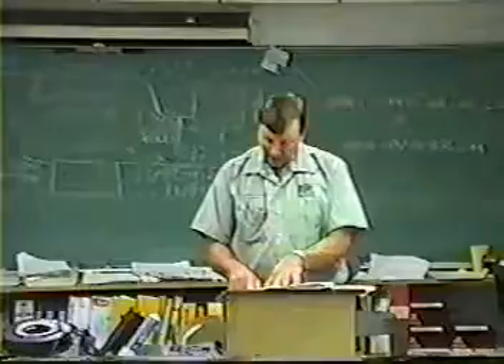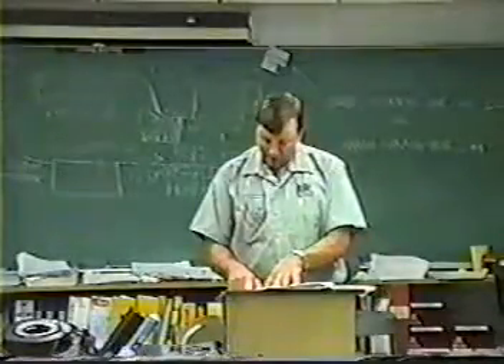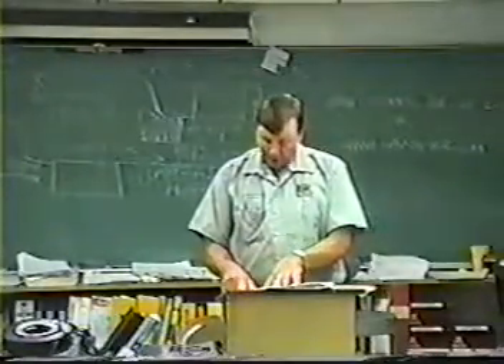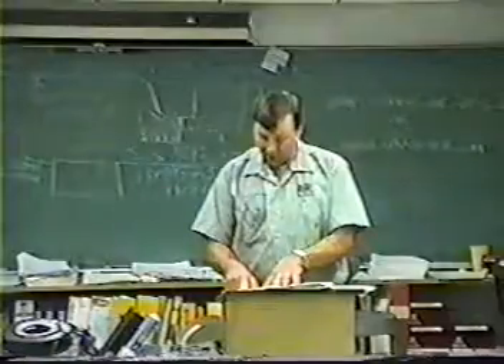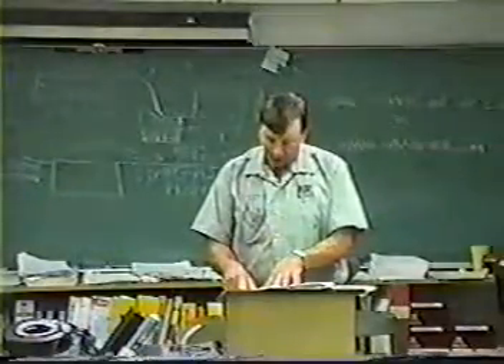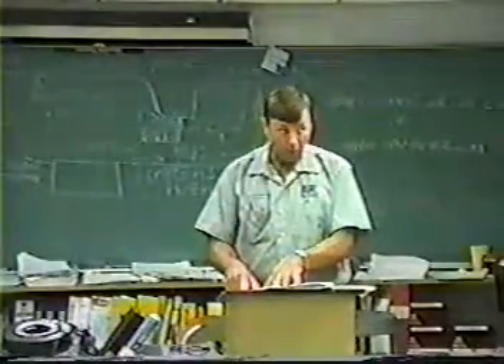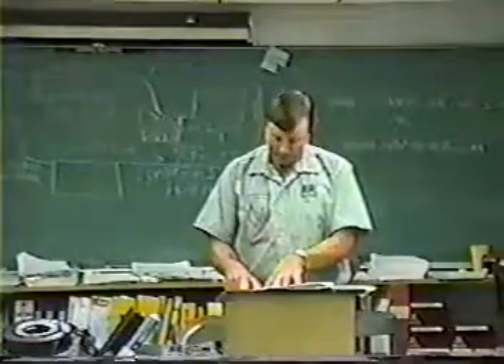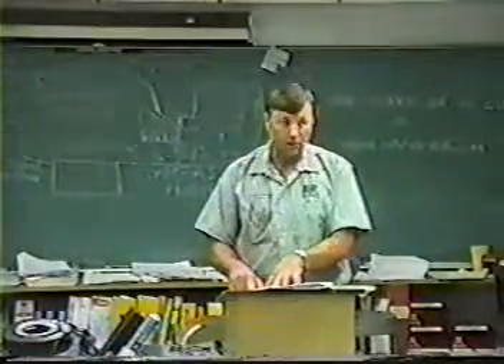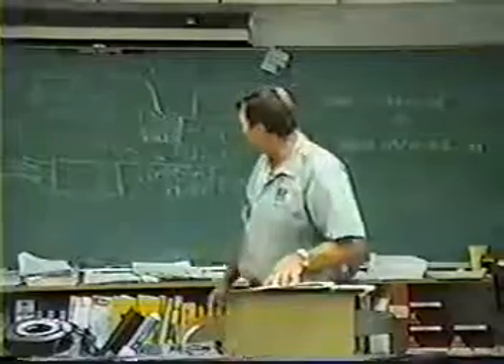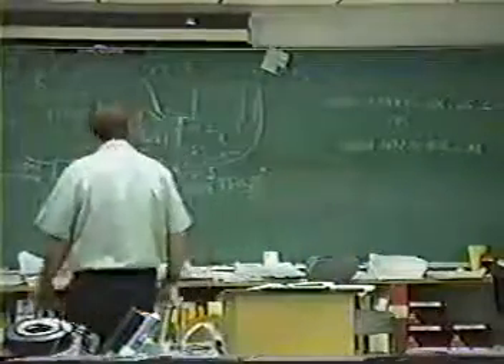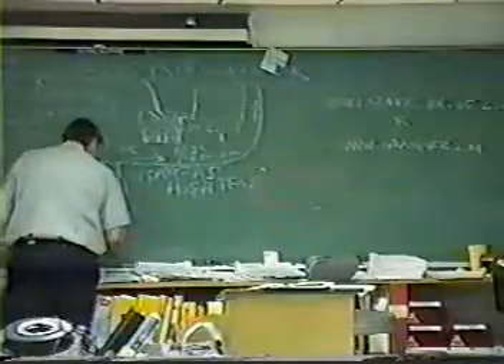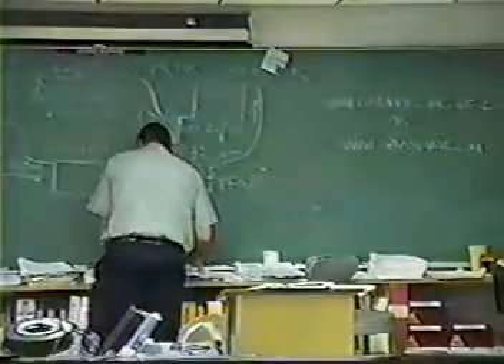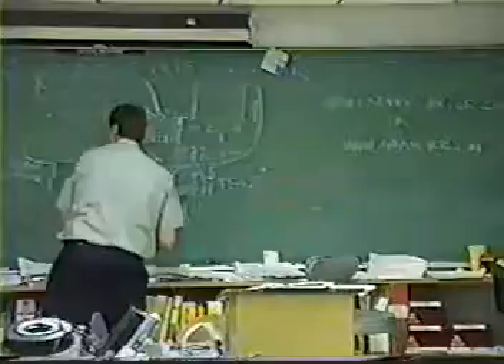The condition and state of refrigerant leaving the accumulator of a system. Now, don't get the accumulator of a refrigeration system and the receiver accumulator of a car mixed up if you've done much work with cars, because it's confusing. We're talking about the accumulator here on the low pressure side. The accumulator is going to be placed right before it enters that compressor. As a general rule, in refrigeration, it's going to be placed right here.